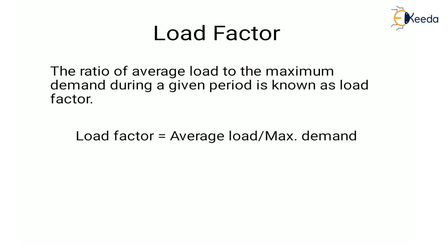Next is load factor. The ratio of average load to maximum demand during a given period is known as load factor. Higher the load factor of the power station, lesser will be the cost per unit generated, because higher load factor means lesser maximum demand. The station capacity is selected such that it meets the maximum demand, so lower maximum demand means lower capacity of the plant, which reduces the cost of the plant. Load factor is always less than 1.